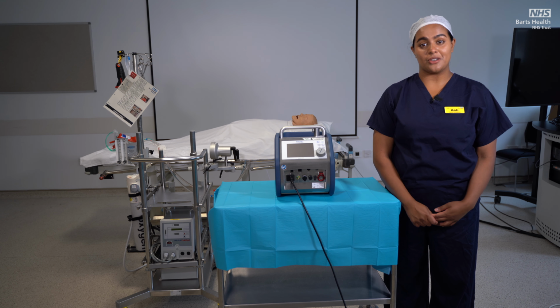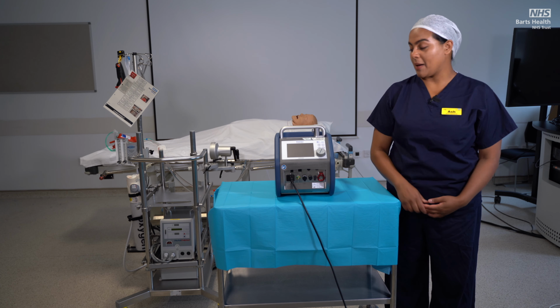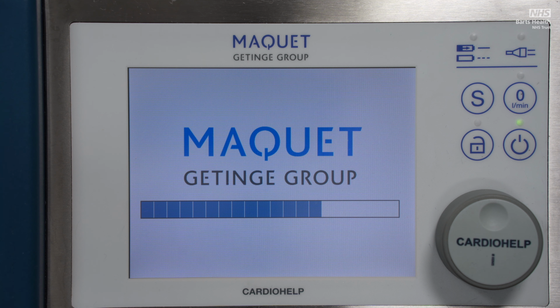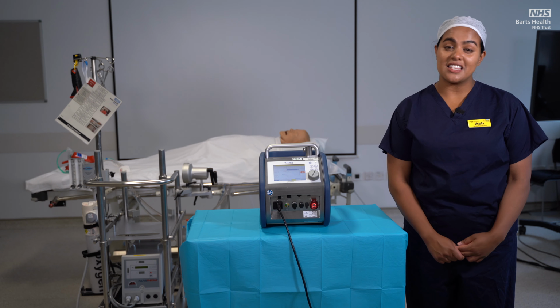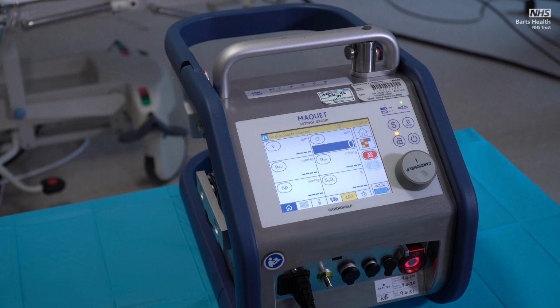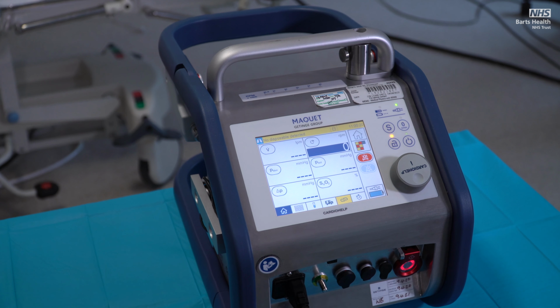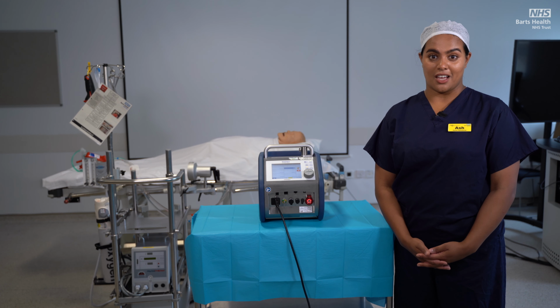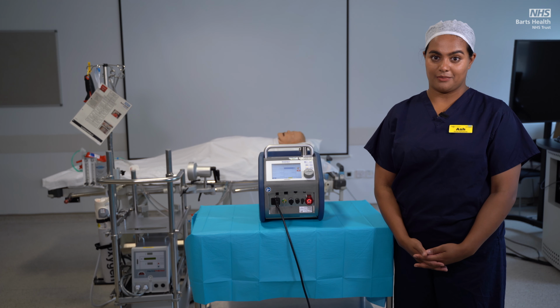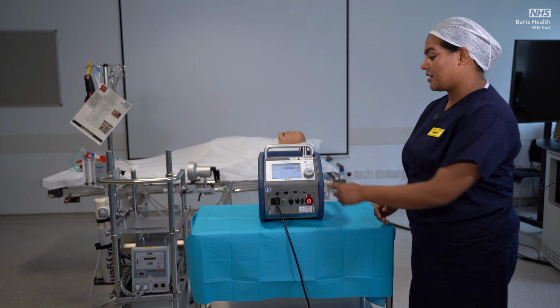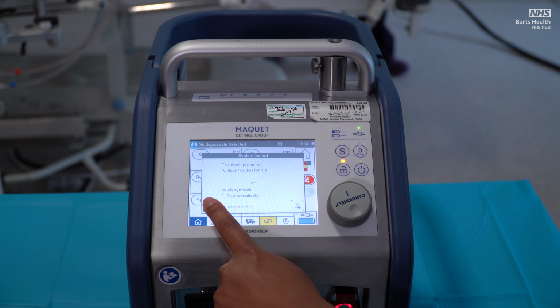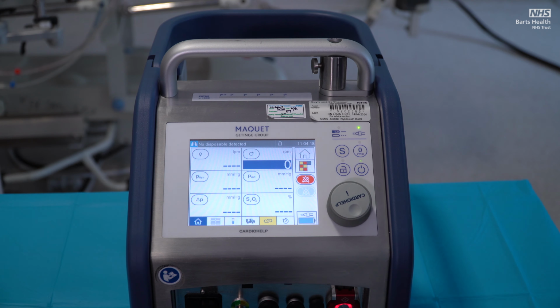The Cardiohelp user interface is a touchscreen, and the power button can be found here. After the self-test, the Cardiohelp will go to the startup menu as seen. The console will auto-lock the touchscreen after 1 minute of inactivity. To unlock the touchscreen, simply touch the touchscreen and press 1 followed by the 2.